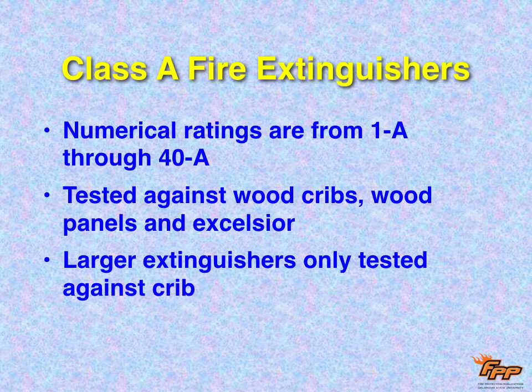Well, Class A extinguishers are for Class A fires, like wood, hay, stubble, paper, common combustibles. They're rated 1A through 40A, and that has to do with the amount of product that it can put out, or the area. The larger extinguishers are going to be tested with these wood cribs, and sometimes they're tested on a wood panel or excelsior.